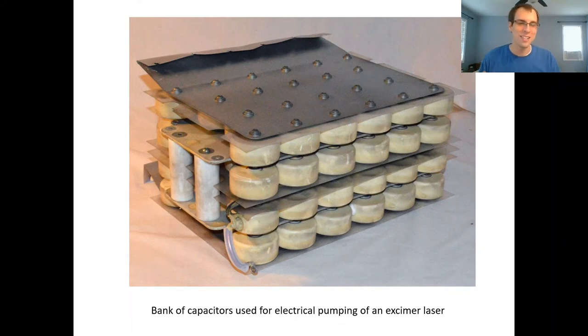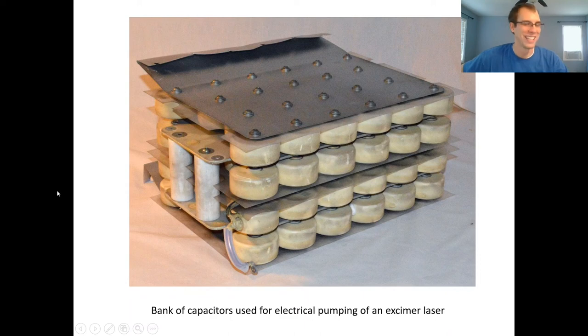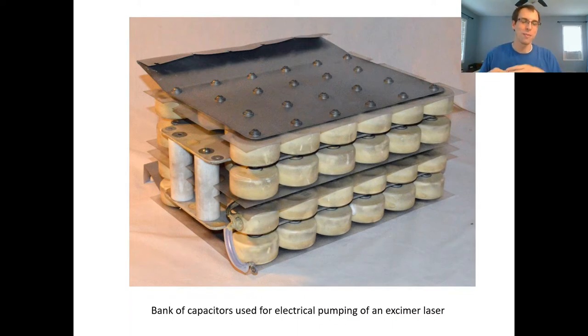And so these are about hockey puck sized, each of these, and they can explode. So I spent a lot of time during my two years in Atlanta changing these out as the laser, these would break apart and the laser would stop working. And you'd have to very carefully drain the power out of them before you started working on it, so you could get a pretty nasty shock.